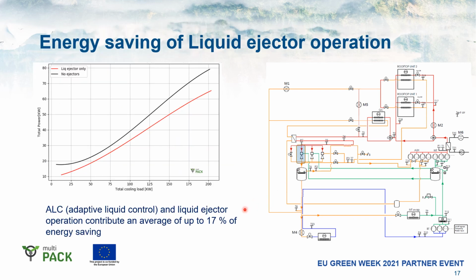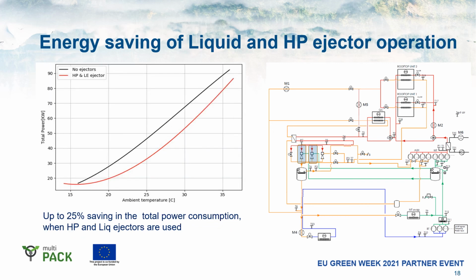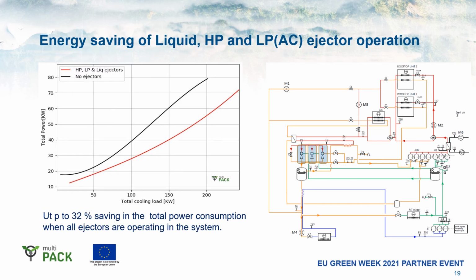So the results obtained were that the ALC mode and the liquid ejector together contributed to about 17% of total energy savings. When we are comparing the operation of both liquid and high pressure lift ejector, we see that savings in the order of up to 25% of the total power consumption could be made. And by comparing the operation of all three ejectors to the non-ejector operation, we could identify that we are saving up to 32% of the total power consumption.